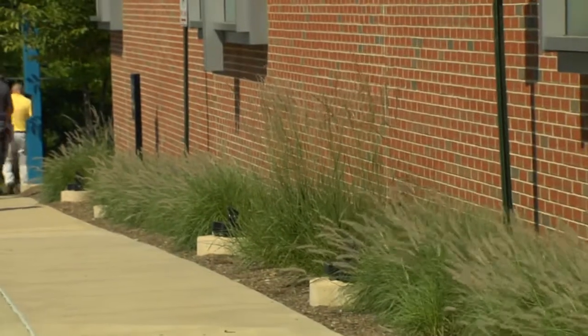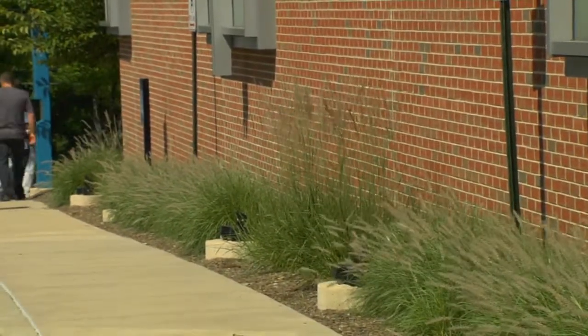Okay, so as we walk around the building, one of the things I wanted to highlight and not walk by without making a mention of, along the ground we have all these wall washer lights. They look like they're halogen. They possibly should be looked at for upgrading to a lower wattage or LED type approach. If they're halogen, they can be as high as 500 watts. There's 7 of them along this wall. That's 3,500 watts, 3.5 kW just on this wall.